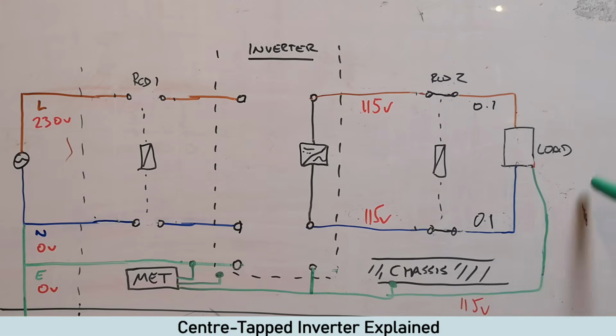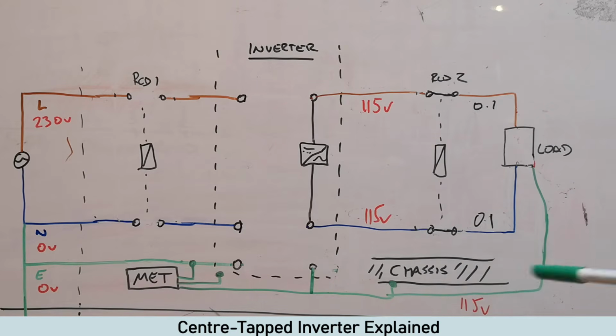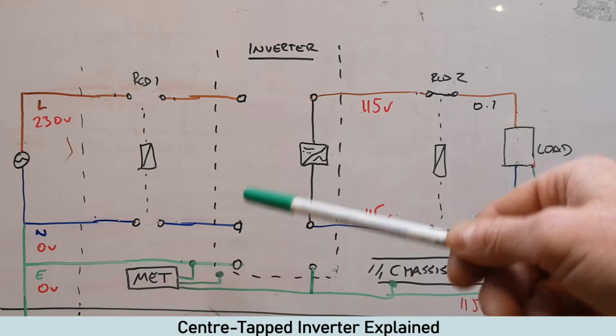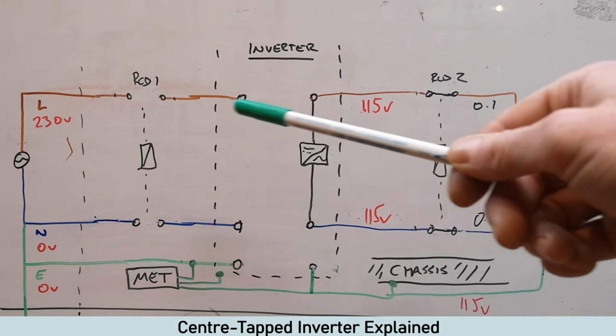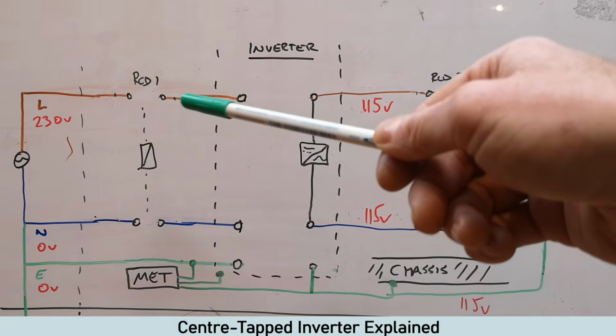If you touch the live and the neutral, you are going to get a shock because then you're part of the circuit. However, if you touch the live and neutral in this instance, you're still going to be part of the circuit. So the RCD is likely not going to trip out because obviously what's going out is coming back in just via you.